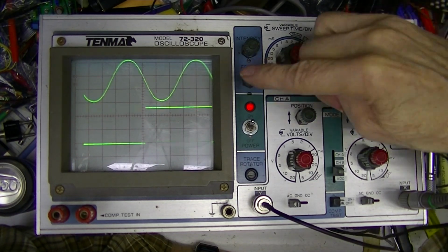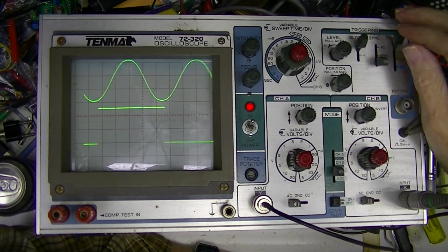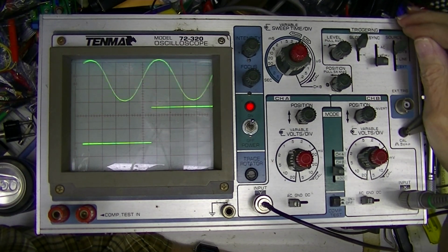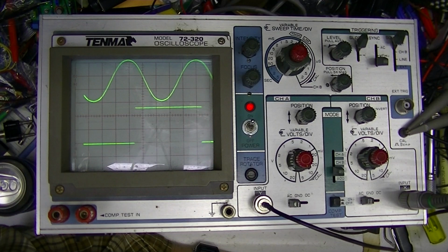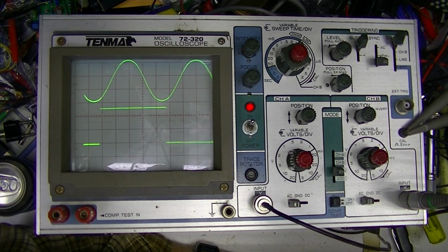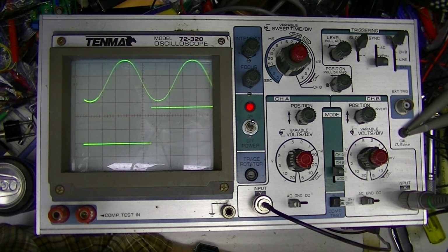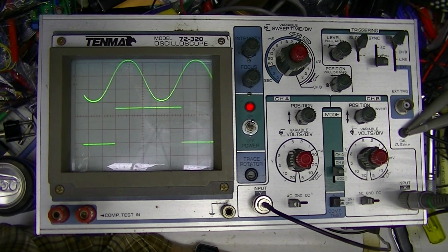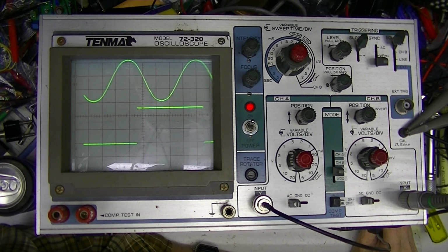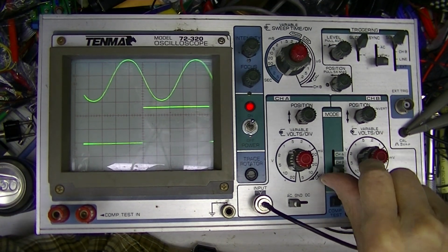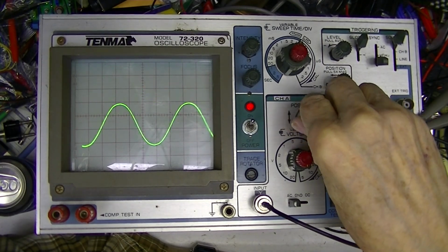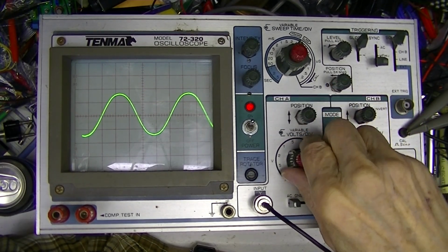Synchronizing internally, which is off A automatically. If I want to synchronize off B, I throw this switch down. I can vary the frequency of the sine wave, and you see I can compare frequencies. When it's not moving, they are almost identical. Well, when it's not moving, they're identical. So we'll go back to just channel A, move it down, give it some gain.